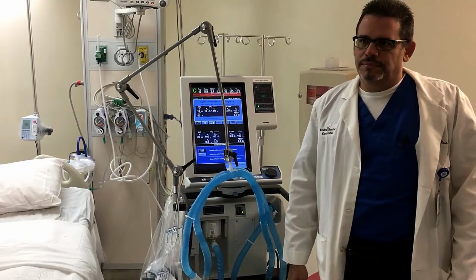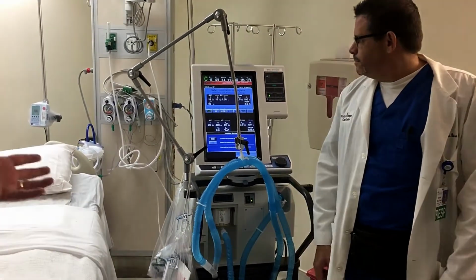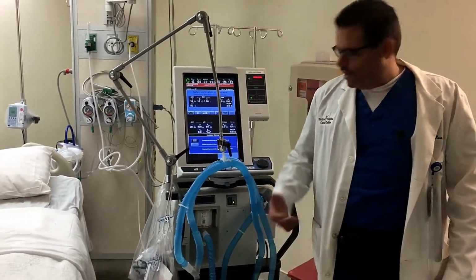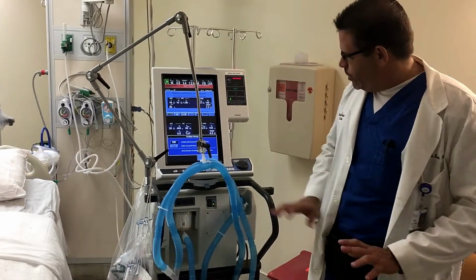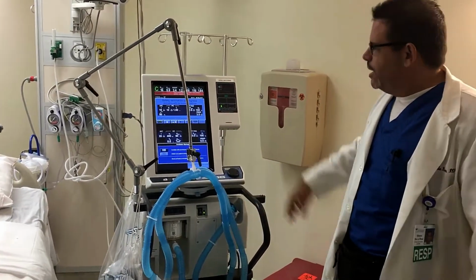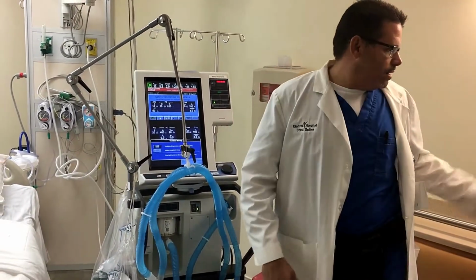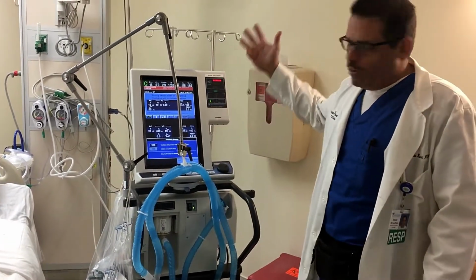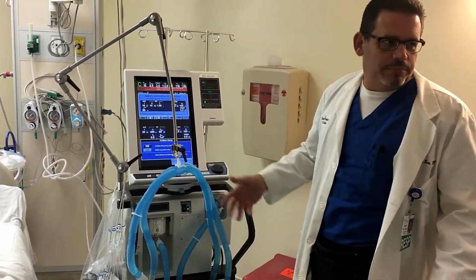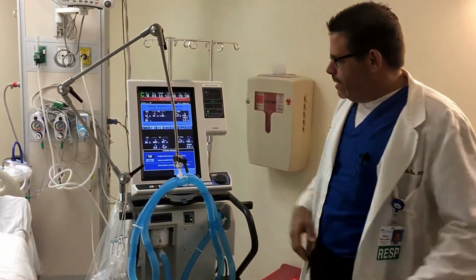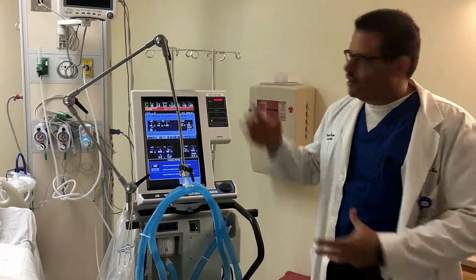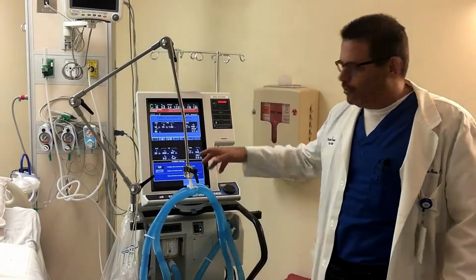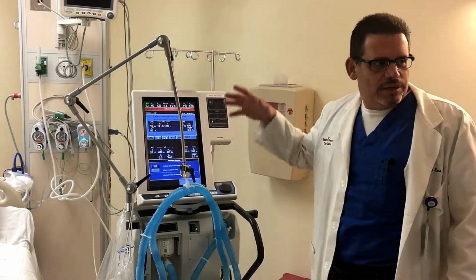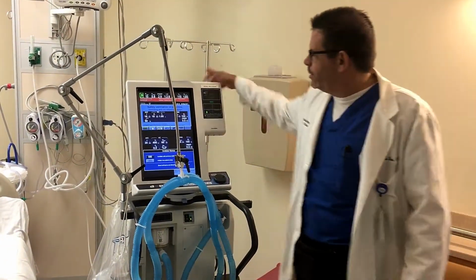But the problem is, we just took away... But what else? I'm sorry. Go ahead. So what we do is we throw everything away. Like I said, everything is single patient use. Then we have the disinfectant wipes. We wipe it all down. It's got a 2-minute waiting period to dry. Once it's dry, they reassemble the unit, they connect it, and they do a quick SST calibration to make sure it's working properly before you place it on another patient.